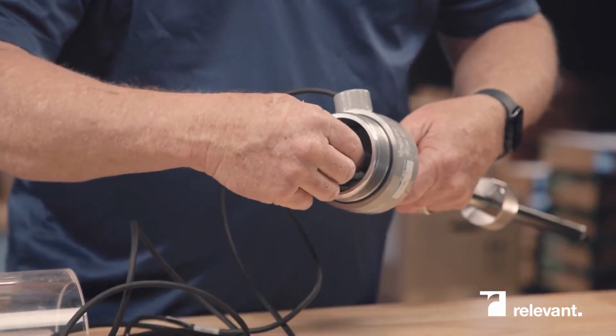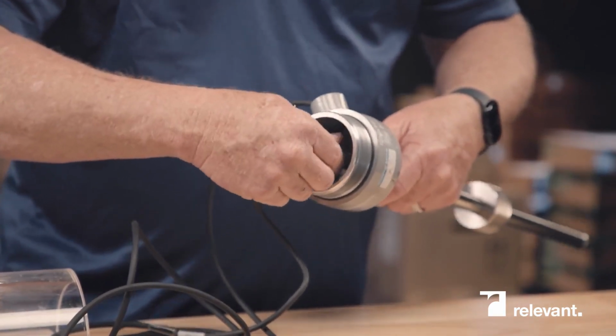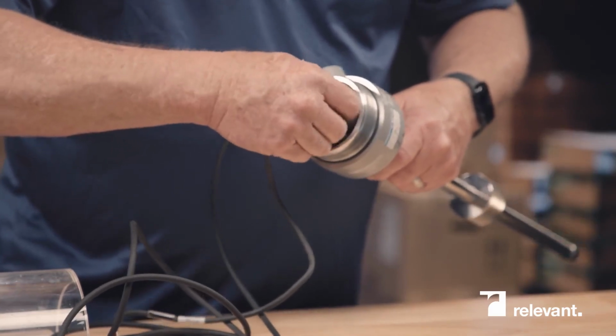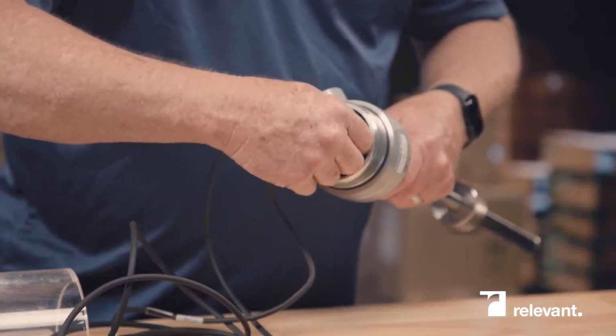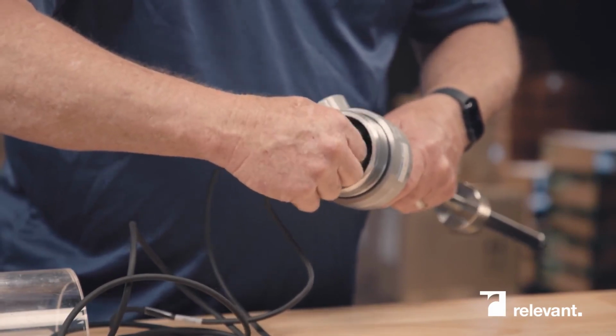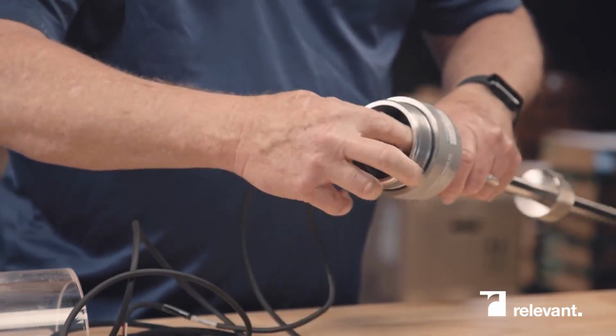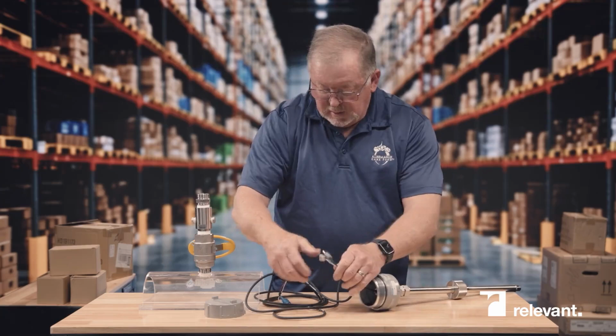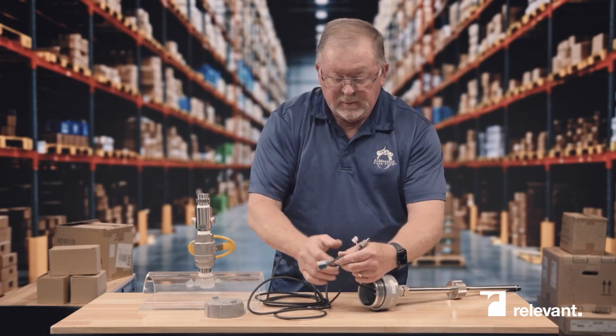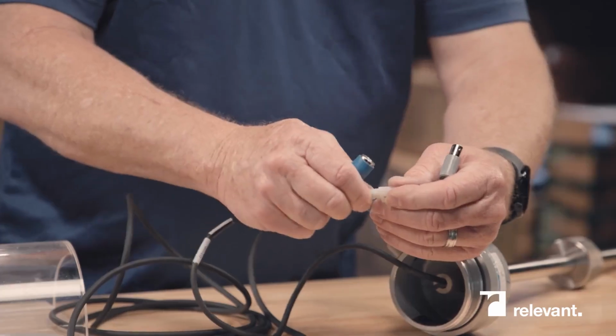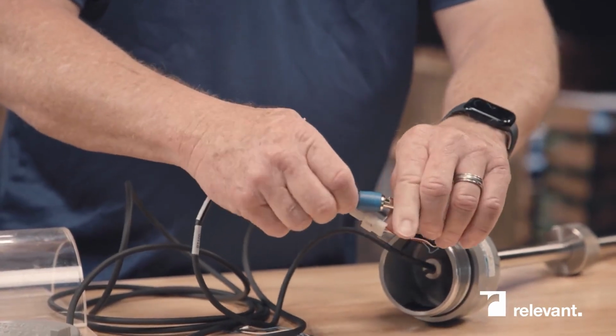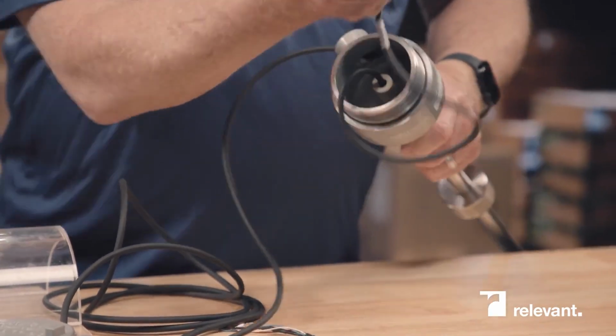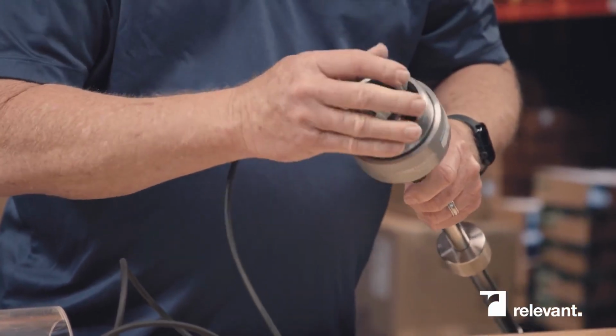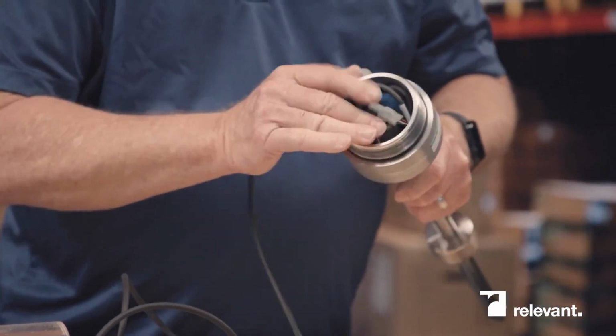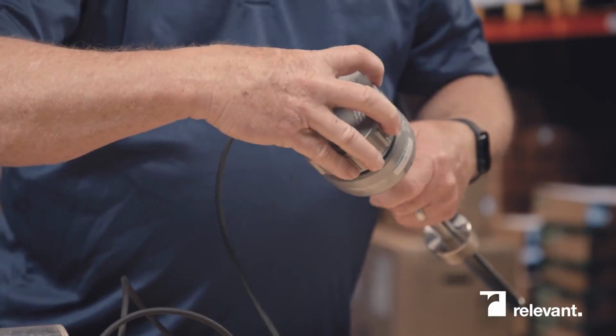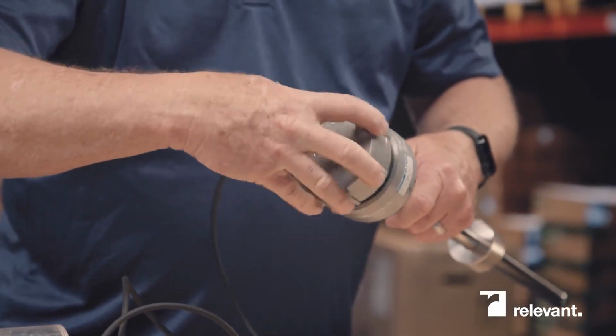For the ease of installation, I have removed the O-rings from the electrode. Once they reach the bottom, you will tighten this down completely, finger tight. Again, no tools required. Reinstall your extension cable, which runs back to your transmitter. Roll these up, tucking them back into the J-box. Reinstall the cover.